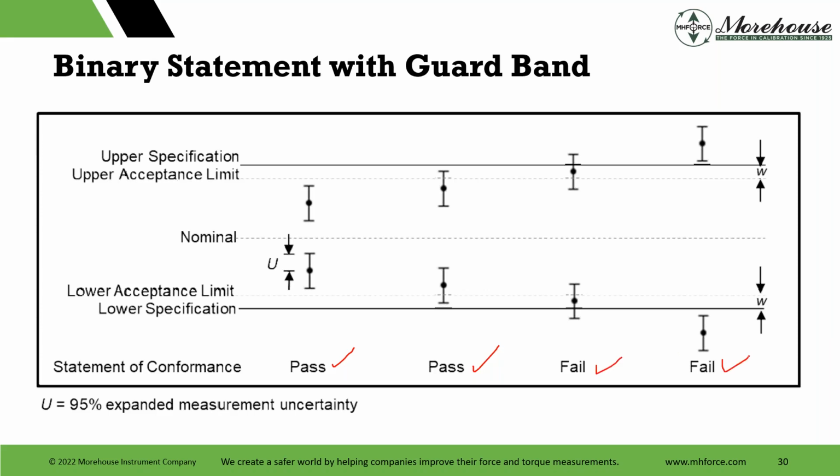That's a fail, and that's a fail. So when we say only 2% risk, what we're saying is only 2% can be over one of these lines. So we would say it's a pass if we draw that out and are out of that whole band, that only 2% goes over the acceptance line.